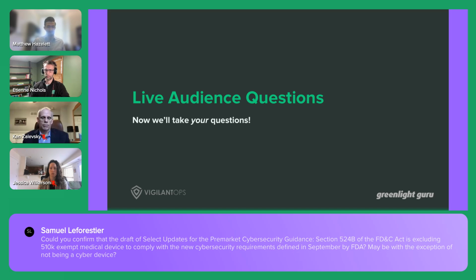However, the guidance still does, because the guidance criteria is based off of whether the device has software, firmware, or programmable logic. So even though there might not be a statutory requirement, the guidance recommendations, including the quality system recommendations, still apply. I will point out we didn't add in all of the quality system regulation references for the fun of it. We do believe that those are important aspects to integrate into the quality system in terms of the development of your device design, and are fair game in an inspection.